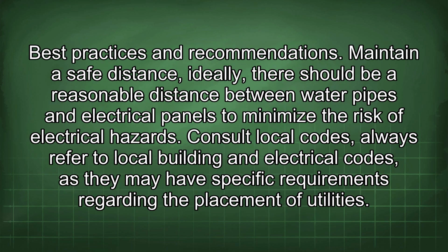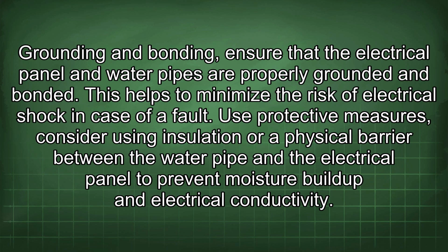Best practices and recommendations. Maintain a safe distance. Ideally, there should be a reasonable distance between water pipes and electrical panels to minimize the risk of electrical hazards. Consult local codes. Always refer to local building and electrical codes, as they may have specific requirements regarding the placement of utilities. Grounding and bonding. Ensure that the electrical panel and water pipes are properly grounded and bonded. This helps to minimize the risk of electrical shock in case of a fault.